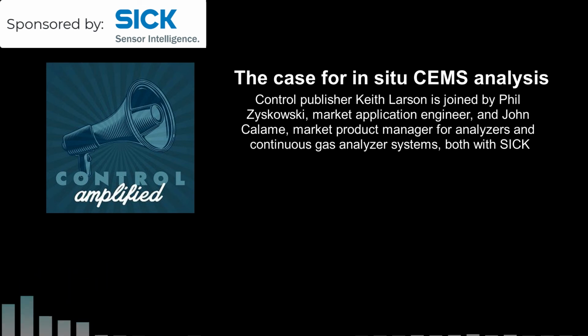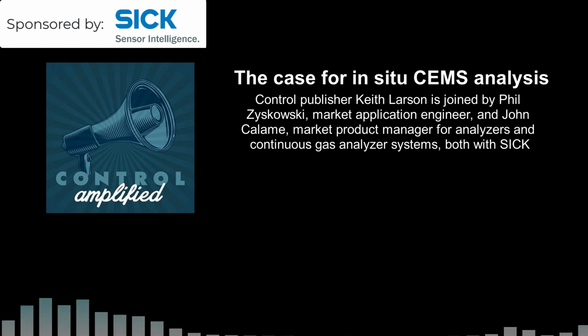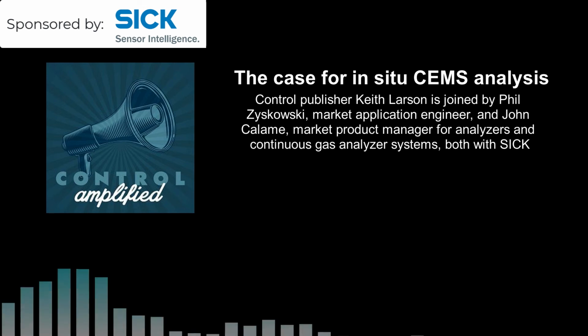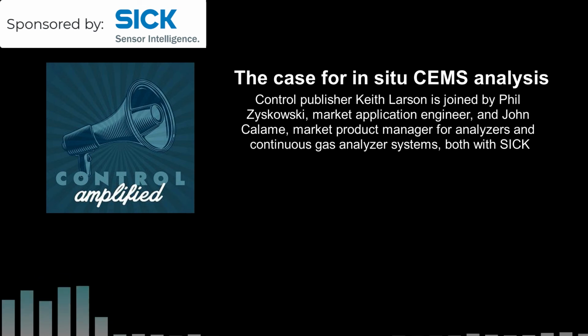So they use a more complicated dilution extractive system that pulls the sample down from the middle of the stack into a shelter at the base of the stack, and it goes through a series of filters and chillers, which takes some time. There's always a risk of the sample changing between point A and point B—some constituents may get entrained in water vapor and dropped out. So our approach has always been to go in situ unless we can't make in situ work.